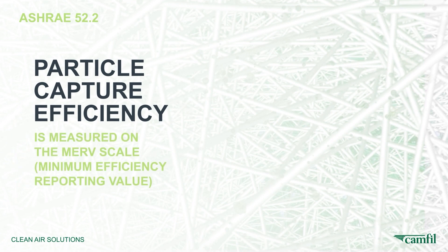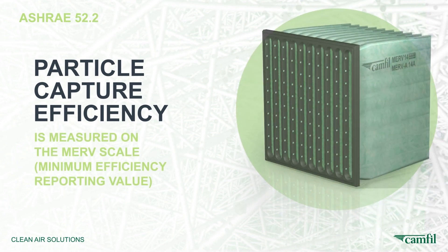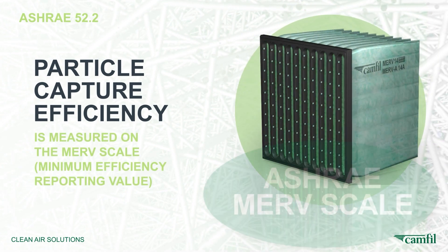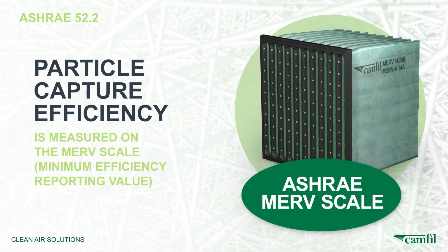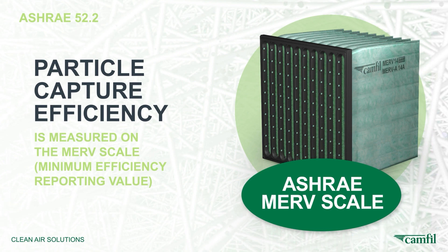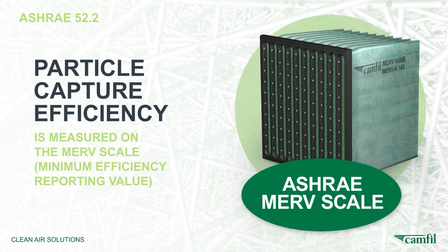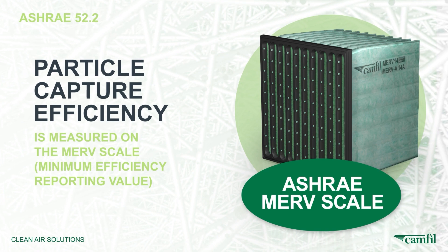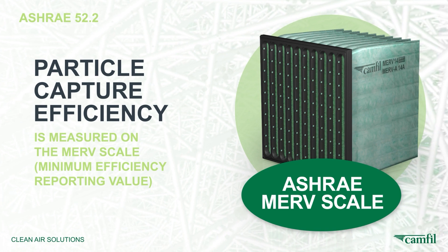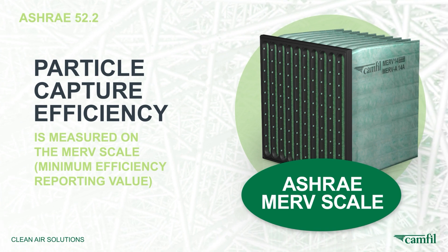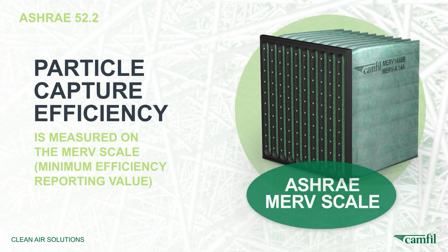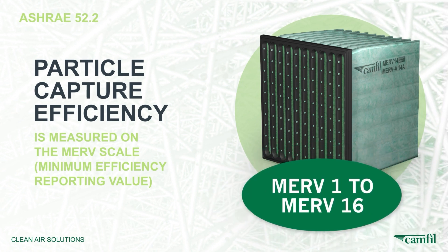In 1999, the ASHRAE committee known as 52-2 introduced the MERV Value Performance Test Standard. MERV stands for Minimum Efficiency Reporting Value. 52-2 is a standardized test that establishes a simple scale from 1 to 16.